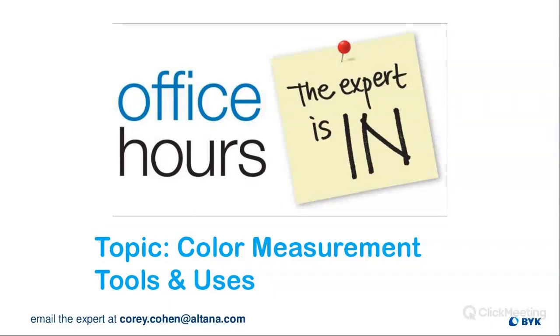You can try sometimes, especially with the profiler, because the aperture is a little bit bigger than with our other color instruments. If you're working in a dusty, dirty environment, it can be prone to getting some dust up in the aperture on those lenses. So you want to take some compressed air like you'd use to clean a keyboard, and hold it not right up against the aperture, because it can spray that chemical into it, and you don't want that. But hold it a few inches from the aperture, and try to knock loose any dust that might be throwing off the measurements. And if all else fails, contact our service department.